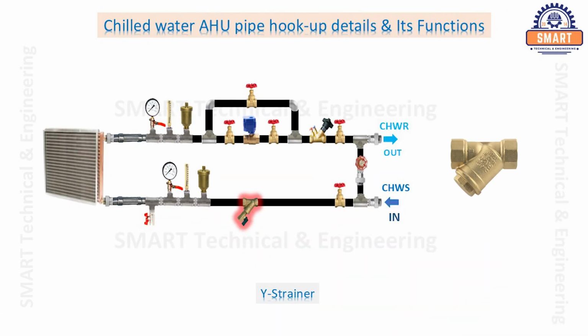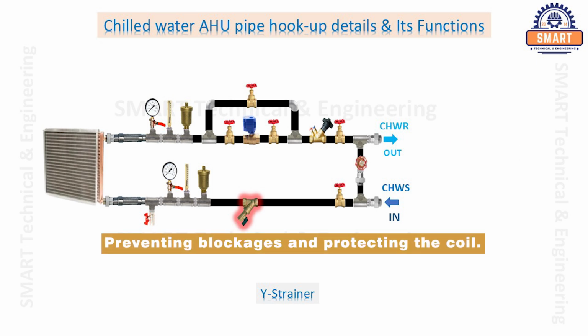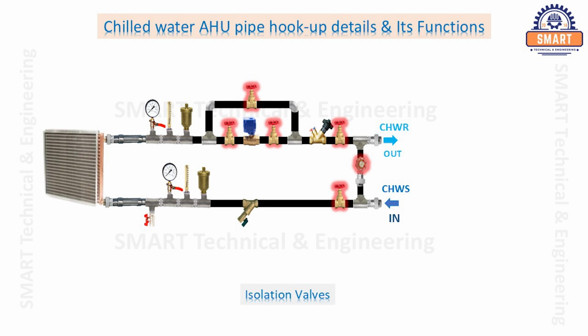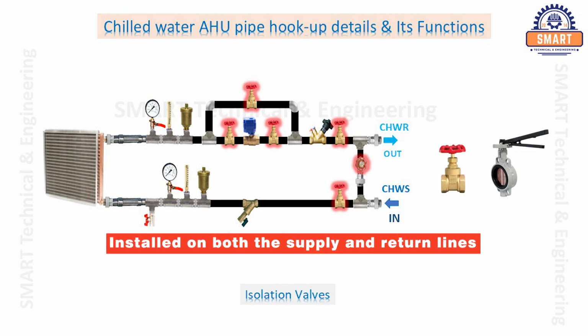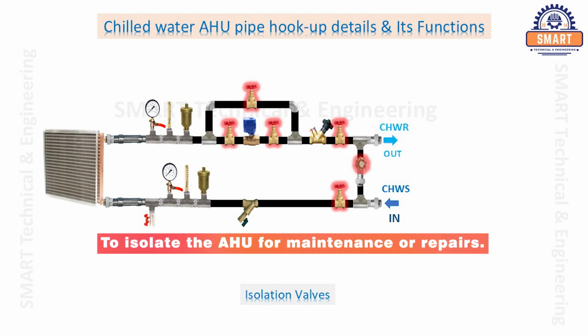Y strainers. Y strainers or filters are installed to remove debris from the water, preventing blockages and protecting the coil. Isolation valves. Gate valves or butterfly valves are installed on both the supply and return lines to isolate the AHU for maintenance or repairs.